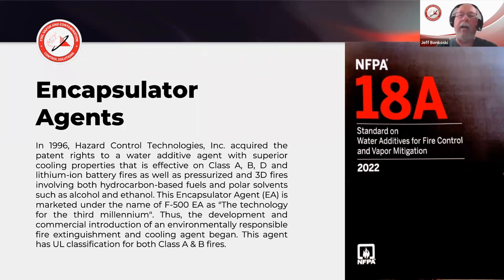But now we have a standard addressing vapor mitigation, and we'll see how this agent achieves that effect, not only on lithium-ion batteries but, as the standard shows, on A, B, D, and three-dimensional fires—fires that foam cannot extinguish. If you look at NFPA 11, Annex A11, it even states that foam is not suitable for three-dimensional fires. This agent works on hydrocarbon fuels as well as polar solvents.